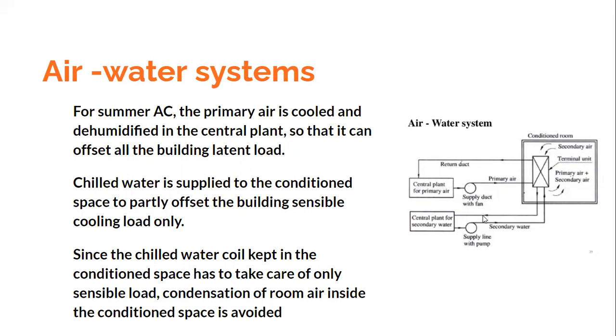Okay, since the chilled water coil kept in the conditioned space has to take care of only the sensible load, there is no issue of condensation of room air inside the conditioned space. So this is the advantage of using the air water system. What is the advantage? The chilled water coil does not take care of the latent load, so it will not dehumidify the air. It is going to only reduce the temperature of the air. So the condensation of room air inside the conditioned space is avoided. Okay, so this is the air water system.